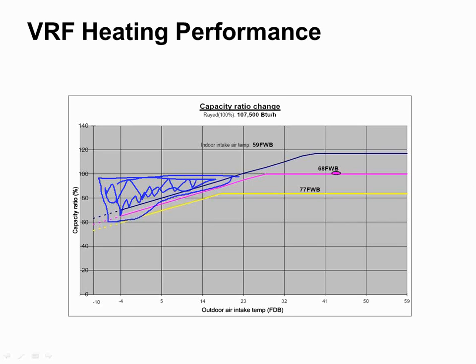The other thing that I could do is I could size my heat pump differently, just like I did on the light commercial residential one. I can size this thing for a -10-degree day if I really want to, right? Basically, I'm going to go up a size. And on a -10-degree day, I'm going to get 100% of the BTUs that I need for my load, which is great. All the rest of the time, I'm going to have too much. I'm going to have to ramp them down. But I could do that if I wanted to.